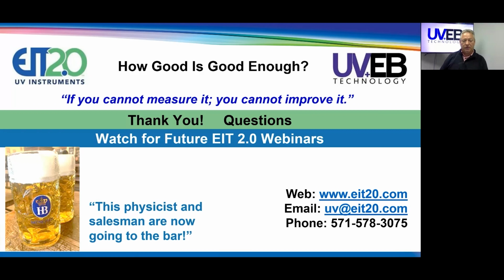Shouldn't, for reliable process control, the UV sensor have the same measurement curve as the spectral absorption of the target? Let's repeat that again. I got it. Yeah. Okay. I would say in an ideal world that would be fantastic, but in the real world, we measure light here, and we don't create sensitivity curves or chemistries that absorb light here.